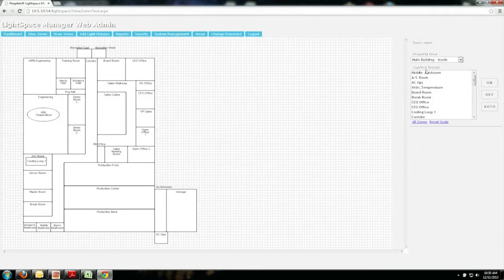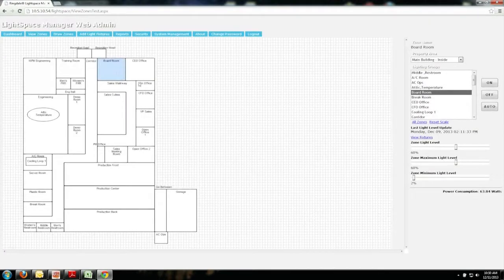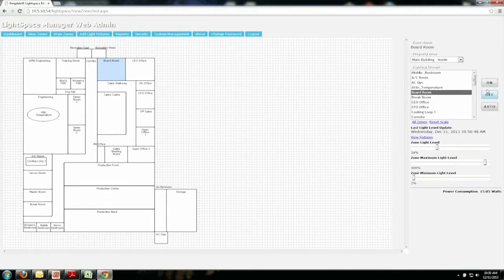Site plans and floor plans can be easily drawn using the zone editor. Once the site plan is complete, zones can be managed by touching or clicking the area and managing it. You can look at the area's current energy use, or take manual control, or set parameters for the input device on that zone, like maximum light allowed, or putting the LSM remotely into off, on, or auto mode.